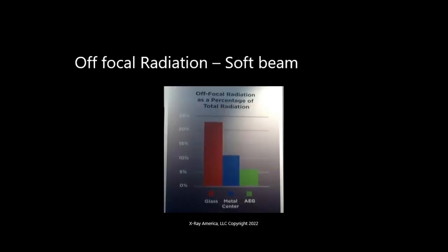So I talked about off-focal radiation. I'm sorry this is so blurry, but in a typical glass tube, you might get over 20% rebounding electrons, or soft X-rays. The metal center tube that I showed you captures some of the off-focal radiation, some of the electrons, so it does minimize some of it. But anode end grounded will get you something around 5% off-focal radiation, so it's much clearer.